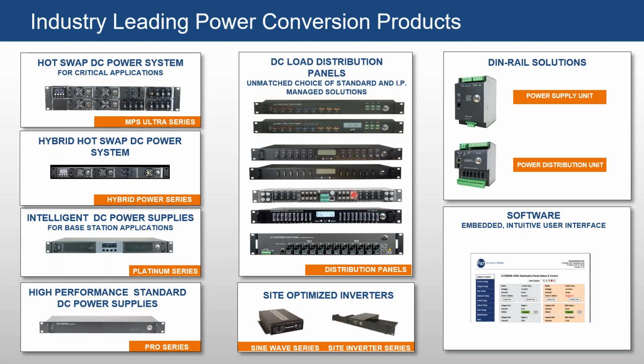Moving to the next one: what is the max current in your distribution panels? As I said, the maximum right now is 300 amperes with our Energy Manager series, the last one I mentioned for 5G. It works for 48 volt and minus 48 volt applications, 50 ampere per output, and a total panel capacity of 300 amperes. The rest of our panels, other than front access, are 200 ampere rated. Front access is 240 ampere.